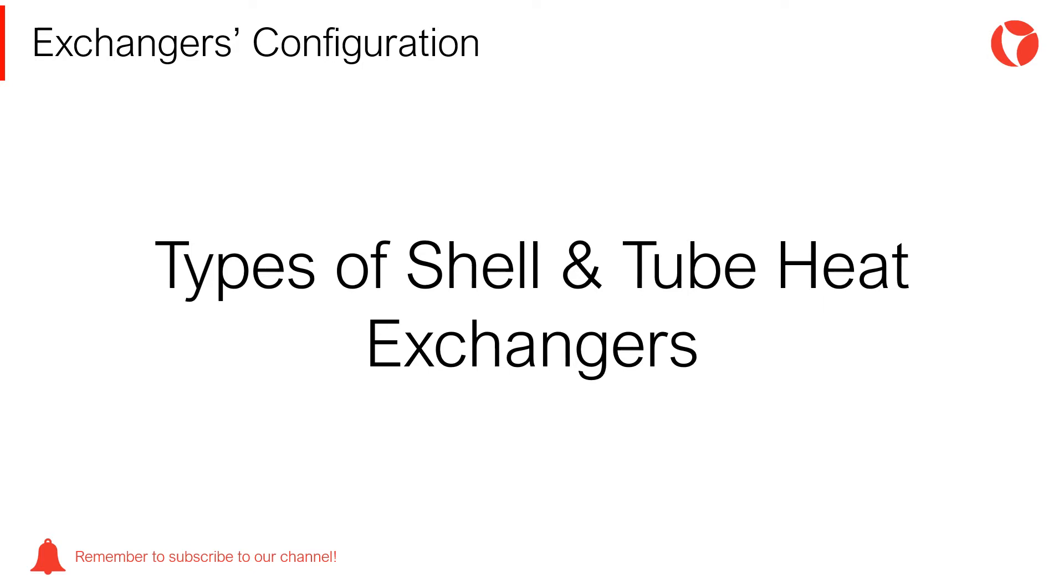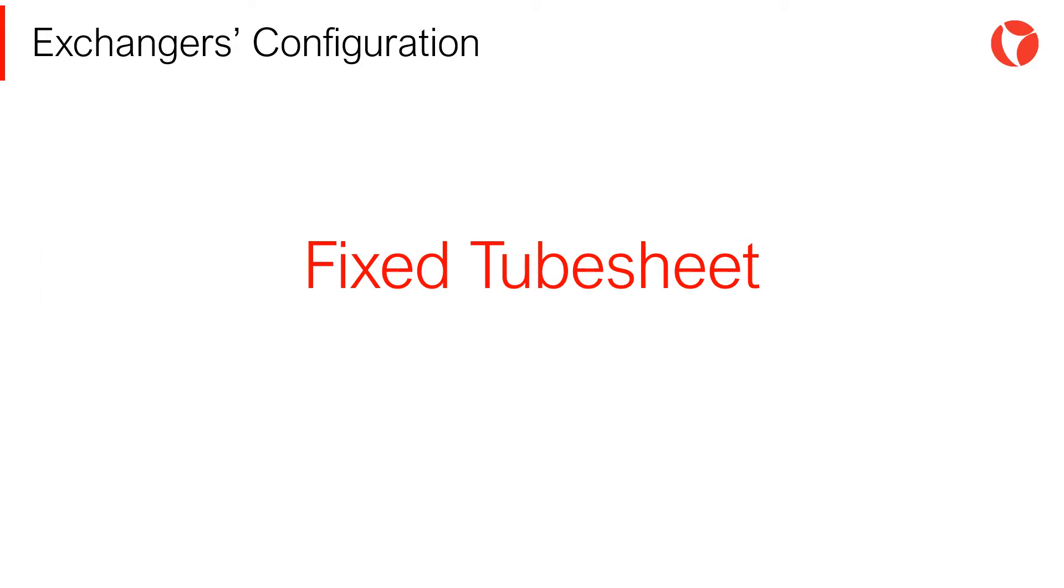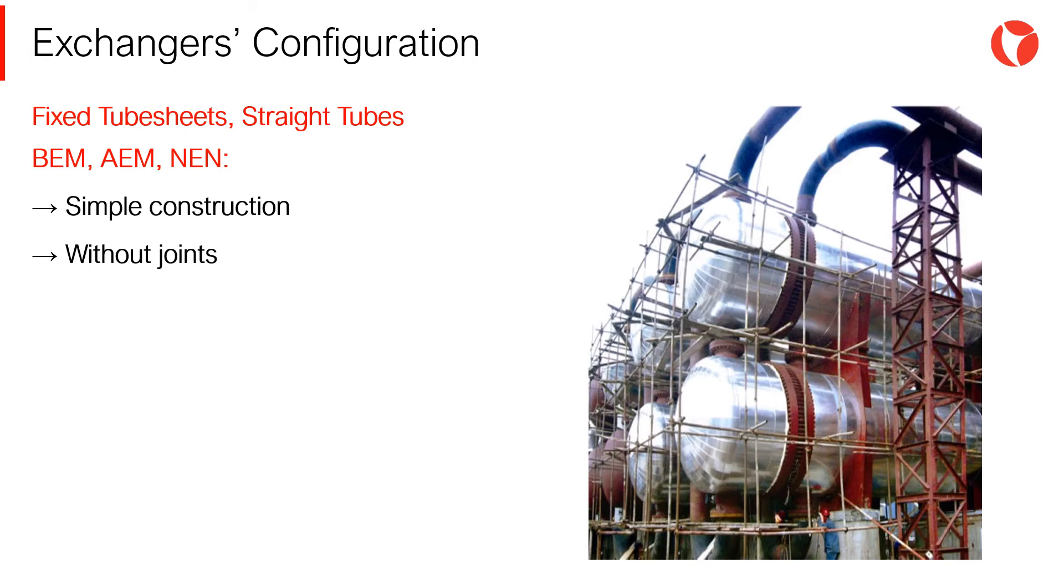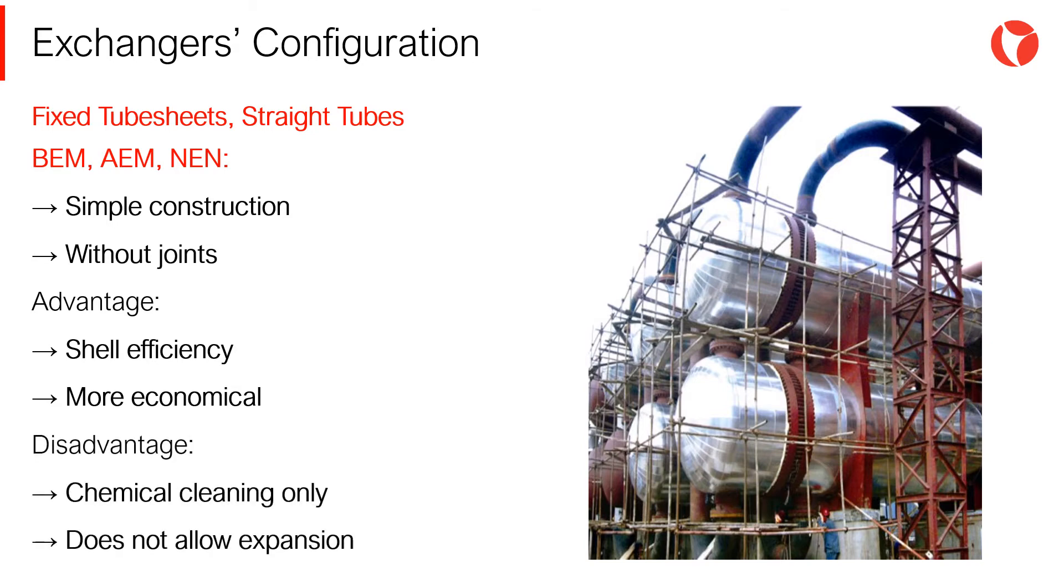Shell and tube heat exchangers are divided into three large groups. Fixed tube sheet exchangers have two tube sheets at both ends of the tube bundle. This type is the most economical of all three types, for the same pressure and temperature. The advantages of this type are shell efficiency and economical fabrication. On the other hand, the disadvantage is that only chemical cleaning can be performed on the shell and this type does not allow thermal expansion.